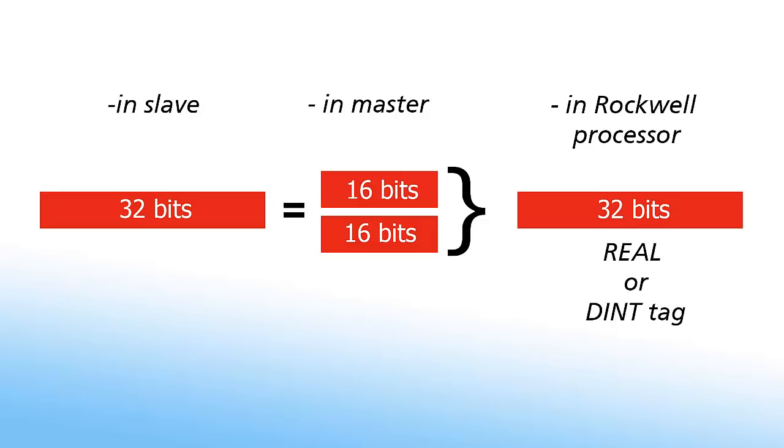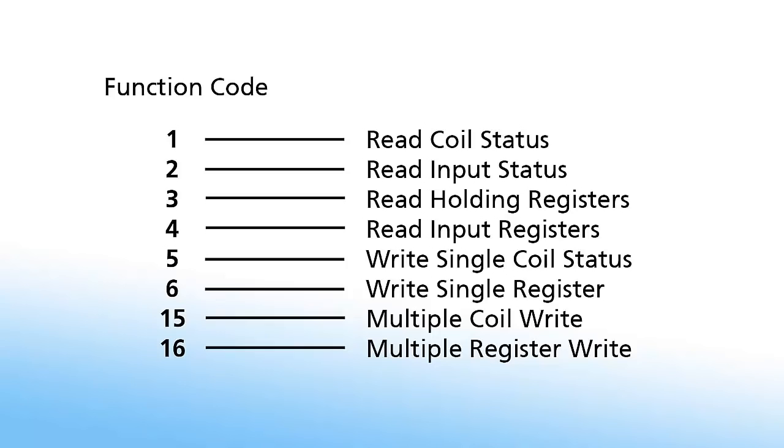This is accomplished by copying the two 16-bit registers to one real tag in the Rockwell processor. Modbus function codes are simple numerical codes that tell the slave which table to access and whether to read or write to that table. Each function code relates to a specific data table address range. For instance, function code 1 is the code to read an individual bit status. Function code 16 is the code to write multiple holding registers. Here are some of the most commonly used function codes.